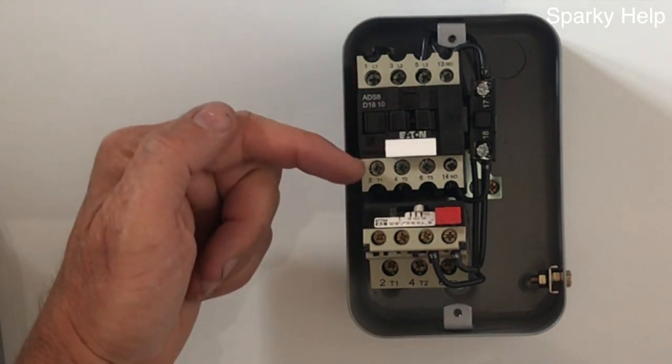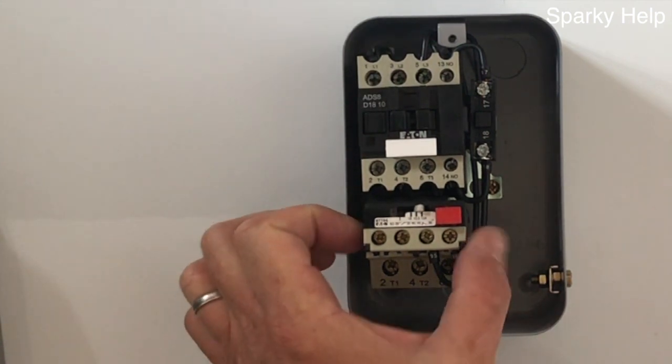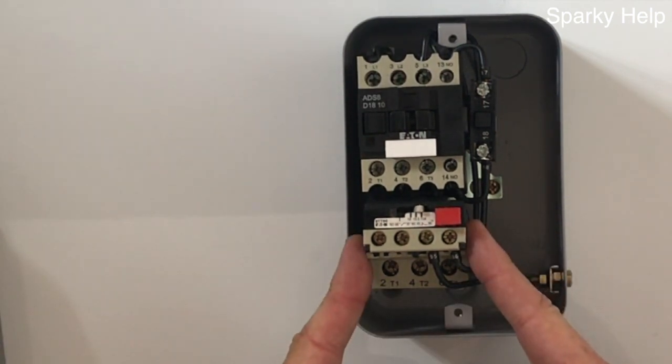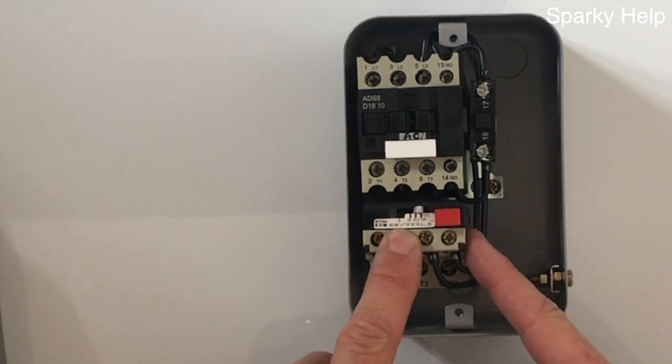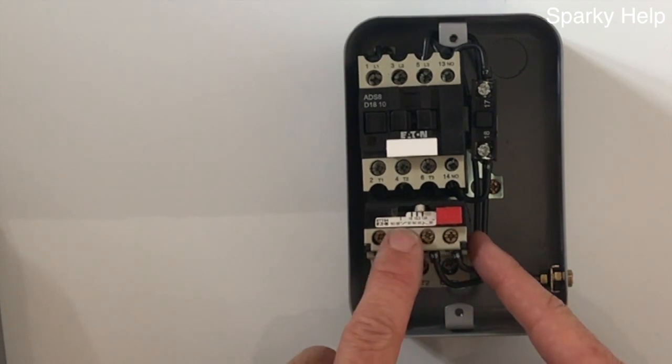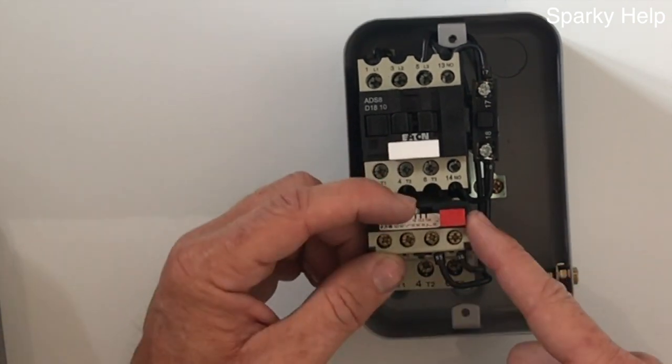What we've got inside is a contactor and the overload. You would have to buy the overload separately for whatever motor you've got. On this particular one it is 13 to 18 amps as an adjustable.